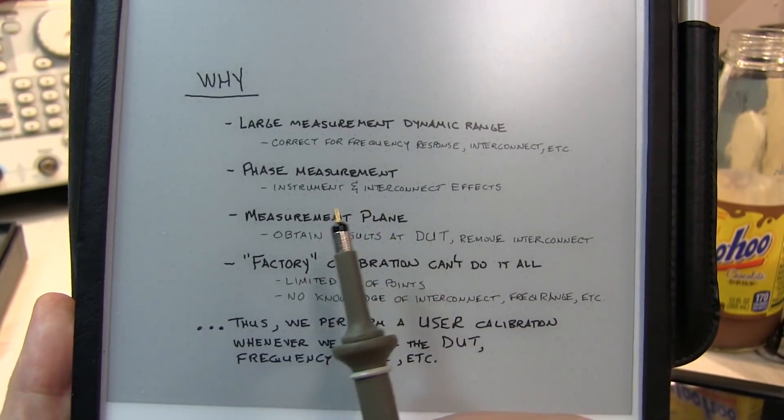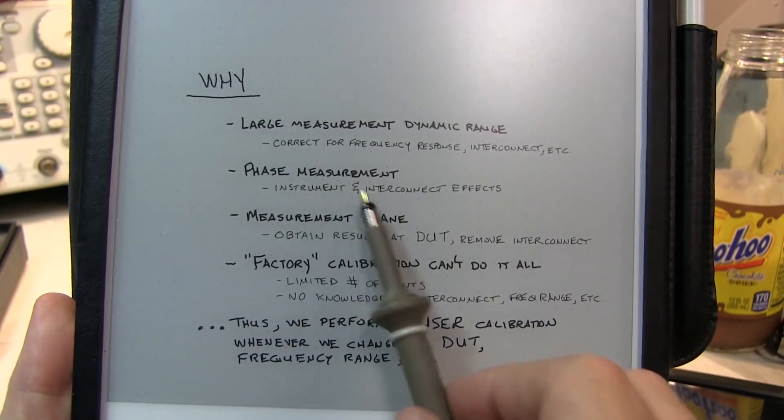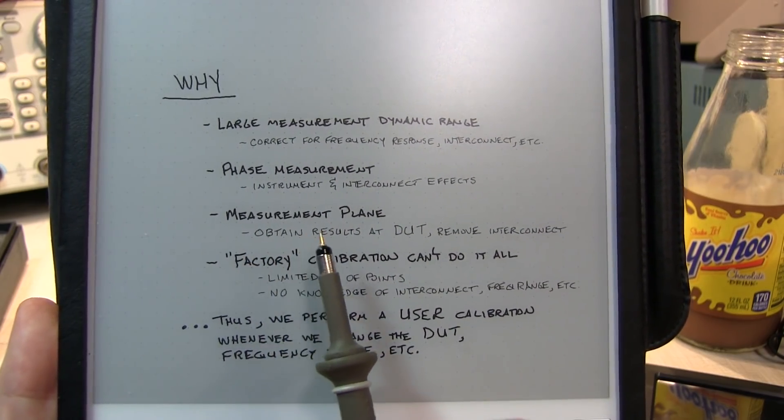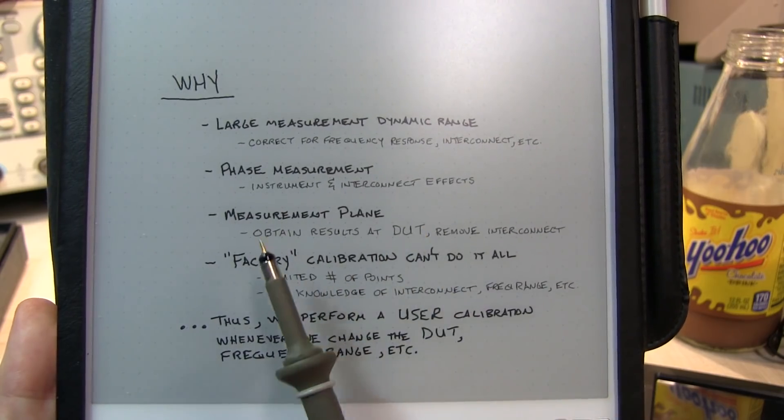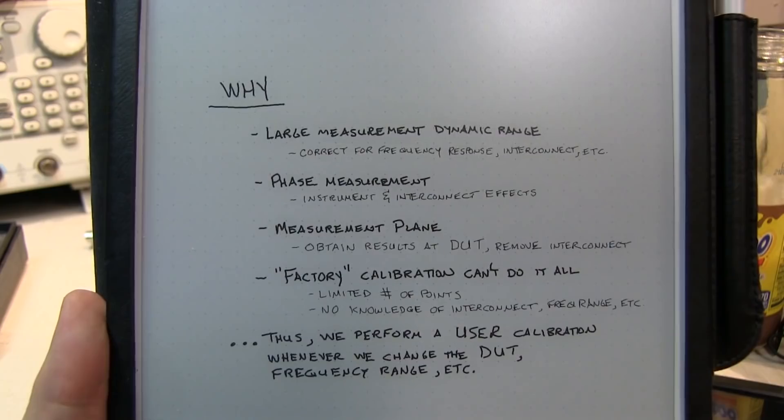We also need to correct for phase response as well as frequency response, especially since we want to measure complex reflection coefficient and complex impedance. We need to really zero out any errors in non-linearity of the phase response of the instrument and interconnect. Another very important reason is to establish what we call a measurement plane or calibration plane. Many times, you can't connect your device under test directly to the terminals of the VNA. You've got to connect it with some coax, and the effect of that coax is that it's going to change the impedance that's seen by the VNA.